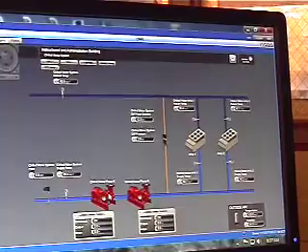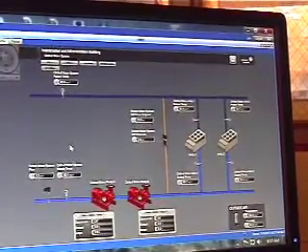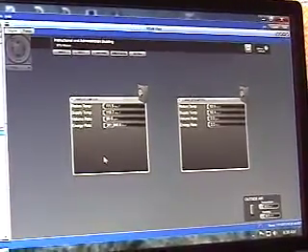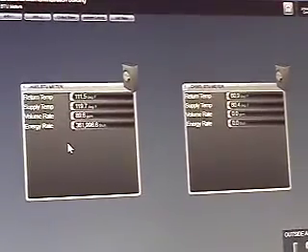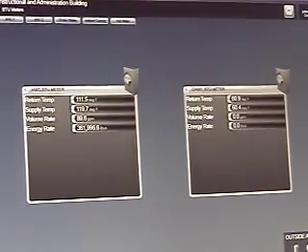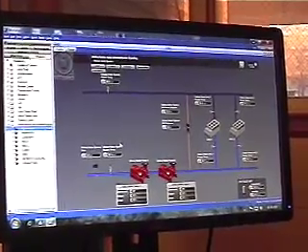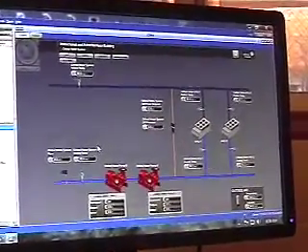Where's the BTU meter for chilled water? He's got a link right here to it. Do you want to know physically or on the screen? On the screen. Okay. Yeah, he's got a little link to it. Is that for both? Yeah. There's another one that we probably ought to add that gives you the ability to totalize and reset and all that kind of stuff. Your energy guy will probably want to know about that. We'll put a link on here to how to reset it. What he has there is just instantaneous values, which probably are good, but not what you're looking for.